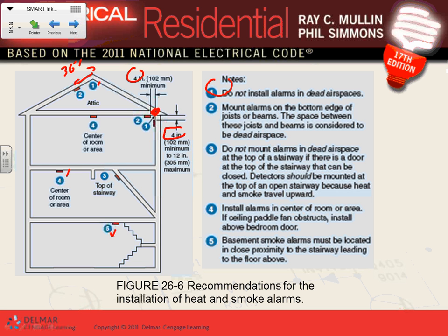So this will give you, if you're an installer, we're not installers. Where do we want to put them? Bedrooms and hallways in front of bedrooms. When you install it, where are you going to locate them in the bedroom? Typically, if you come over here and move like 4 feet away from the door and you put it right there, don't get it closer. As long as you don't get closer than 4 inches from the walls, you're good to go. Can I have thumbs up, Chad?